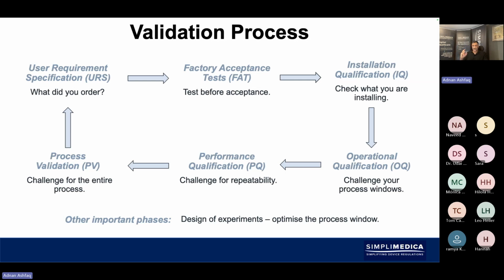The reason why, again, is because of the number of occasions where I've seen that there's been issues with the supply. It could be something like the crate or the pallet was the incorrect size when it was delivered and shipped to the manufacturing site. It fell off and it damaged the actual equipment. Then when it gets to doing your installation qualification, you suddenly realize that it's failed because it wasn't shipped correctly. The whole point of then staging this is that it gives you the opportunity to check everything stage by stage. So only then, once you've satisfied the FAT, you would then move to installation qualification to check what you're installing.